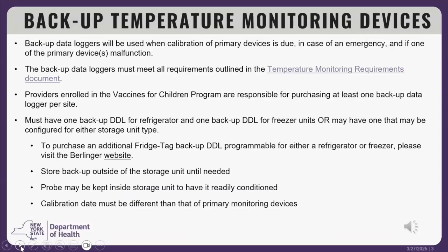VFC providers are also required to have a minimum of 1 backup continuous temperature monitoring device on site for both refrigerator and freezer, or one that is programmable for either a refrigerator or freezer. Backup DDLs must meet all of the same requirements as the primary devices. The backup device is used in case of equipment failure or when calibration testing of the current device has expired.